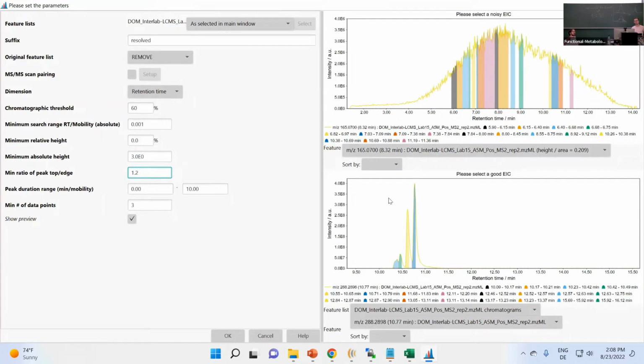What you, for example, have here is probably some stuff that is stuck in the acetonitrile because it goes up with the gradient and goes down with the gradient in the end. If you run the same acetonitrile, you probably have the same contaminations, and you have a starting point for the optimization. You should always verify that the parameters that you used previously work for new data sets. But if you have your chromatographic setup and you always run the same HPLC method with the same solvents, you have a starting point, and you can optimize from there, check, is it fine, or do I get garbage out? And if you get garbage, then you should look into the data and check where something is going wrong.